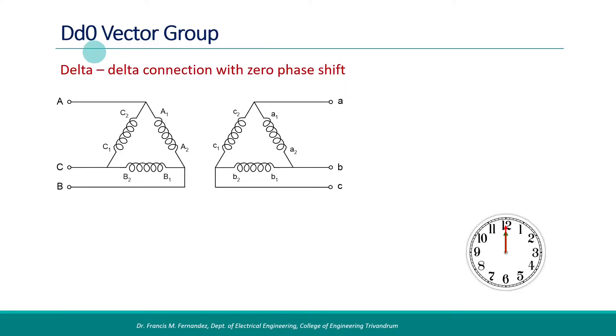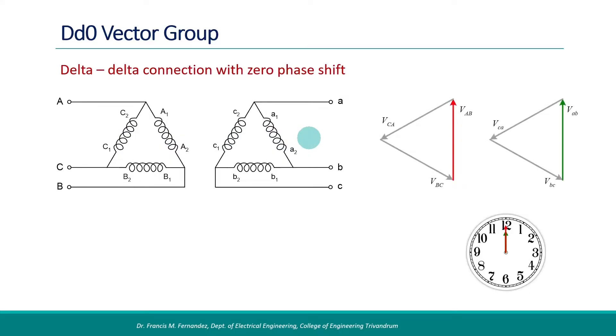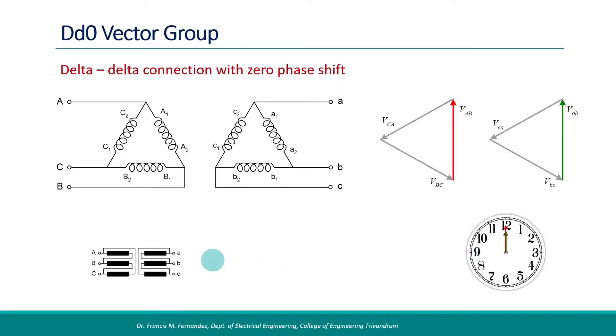The next type is the DD0 vector group. It has a delta-delta connection — both primary and secondary windings are delta connected. In the phasor diagram, line voltages are in phase with the corresponding primary side voltages. The phasor positions of line voltage VAB is considered for phase angle representation, and since there is no phase difference between the primary and the secondary, the clock position corresponds to zero hours. We can have the simplified connection diagram and also the displacement diagram.